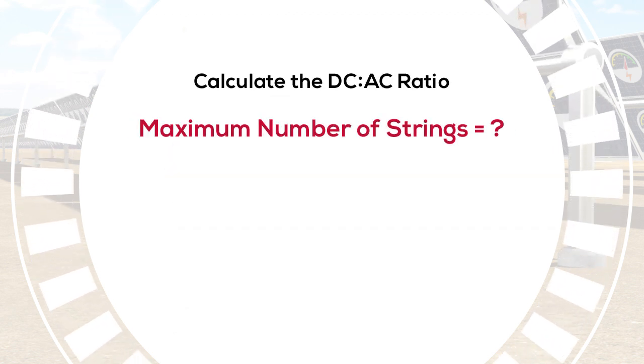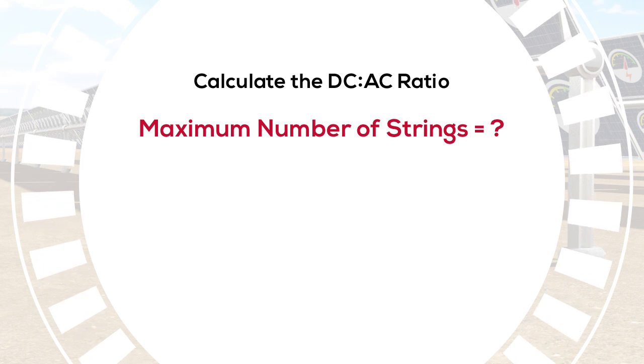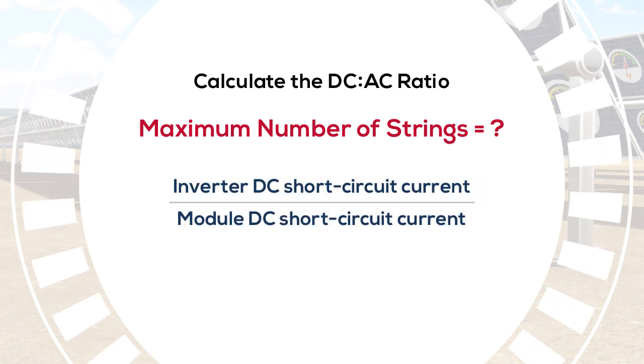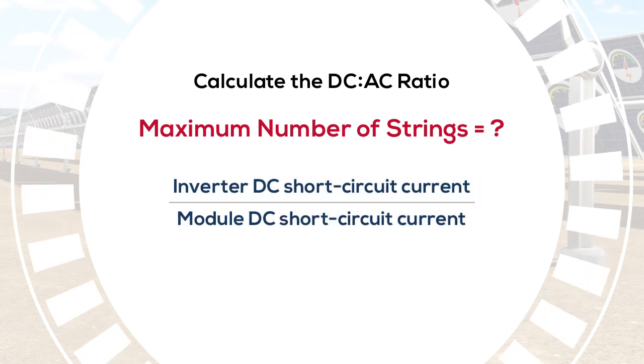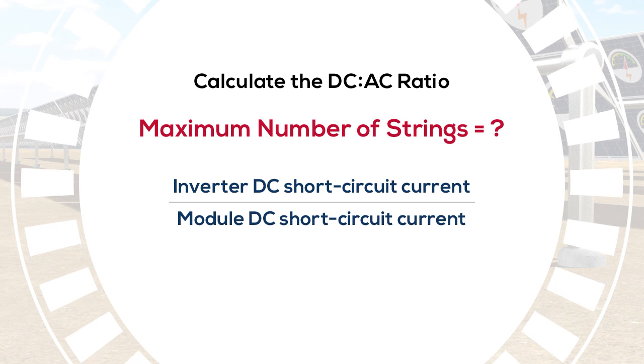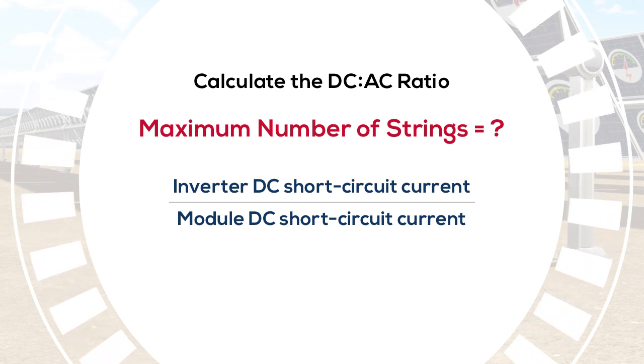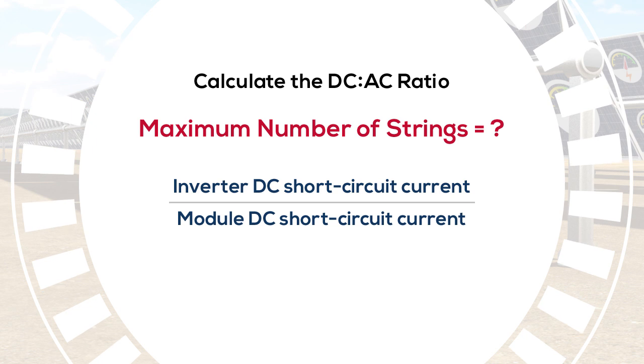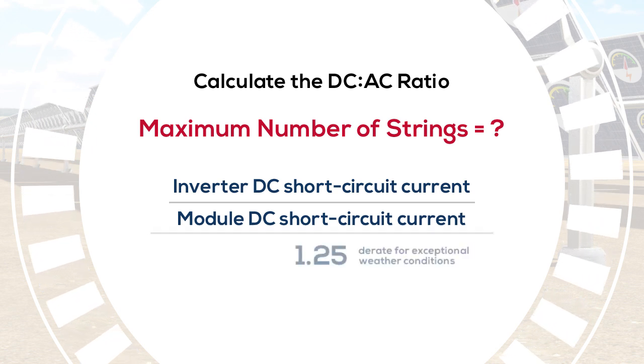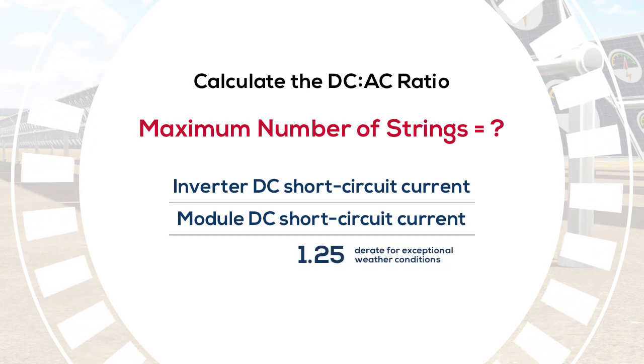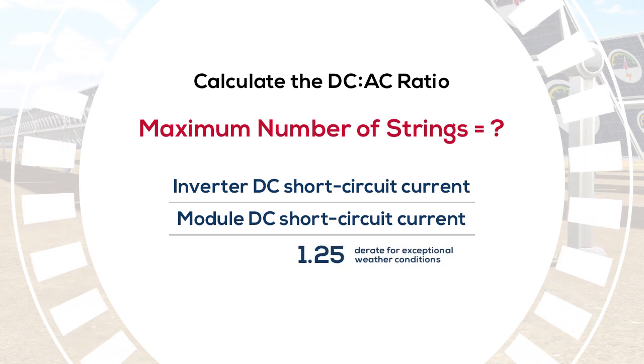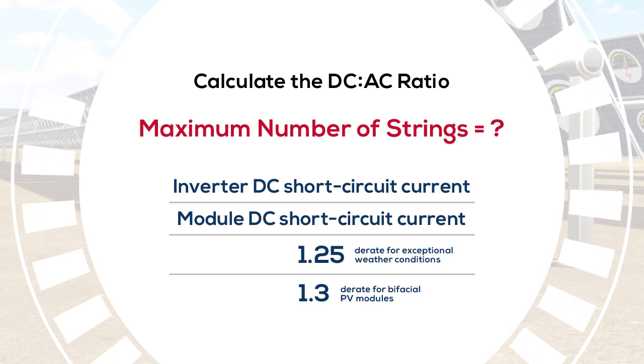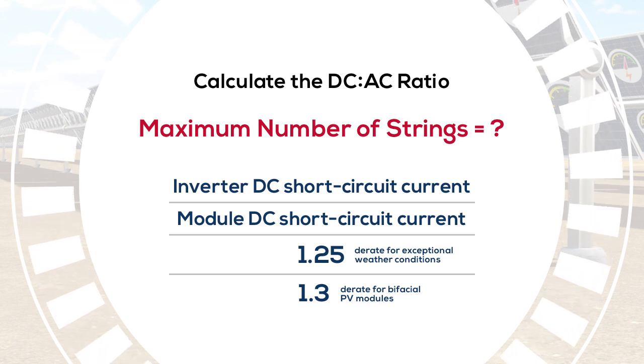The first step is to calculate the maximum number of strings. It's the short circuit current rating of the inverter divided by the short circuit current of the module. You also have to apply two D-rate factors per the National Electric Code: a 1.25 D-rate for exceptional weather conditions and a 1.3 D-rate for bifacial PV modules.